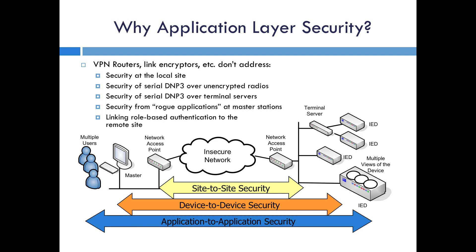There are three types of security commonly deployed in communication networks today. First is site-to-site security, which includes the use of a virtual private network, or VPN, and protocols such as IPsec to secure the link between two locations — for example, between a master station and a substation. It does not secure the networks at those locations, and physical security measures like locks and guards are still necessary. Second is device-to-device security, which includes protocols such as Transport Layer Security, or TLS, to secure the complete TCP connection between two devices, similar to accessing your bank through the internet. However, TLS only works on IP networks and is lost if a message is forwarded over radios or serial links. It also does not address rogue software applications installed on a device.